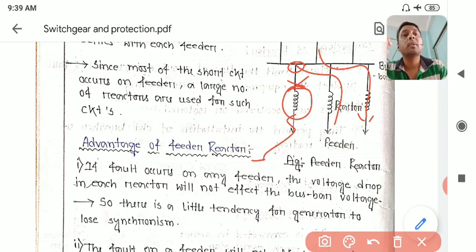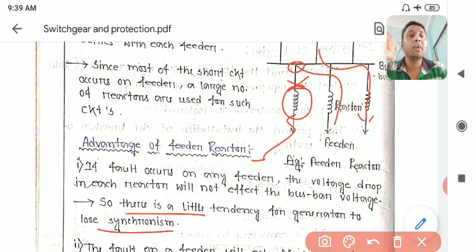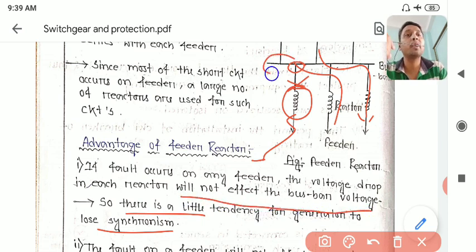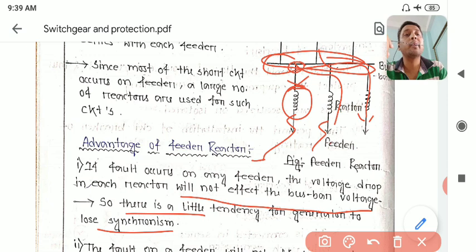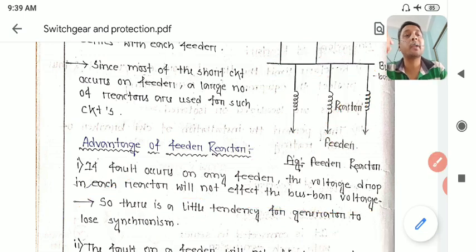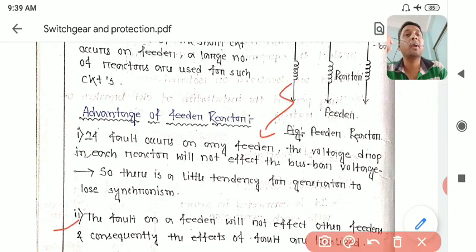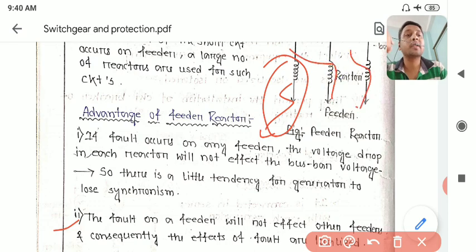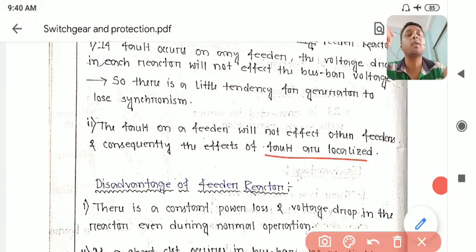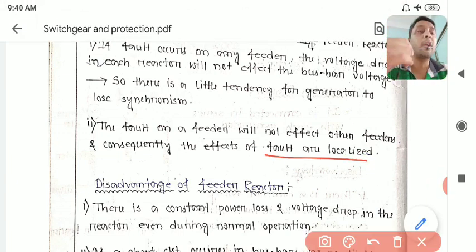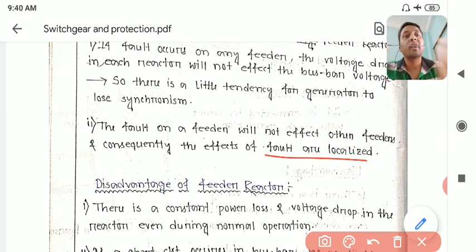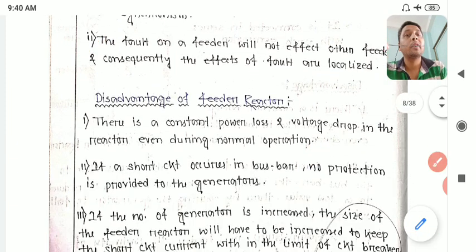Since the voltage is not zero, the generator will remain in synchronism and other feeders will continue to get current. There is only a little tendency to lose synchronism, and the voltage drop in each reactor will not affect the bus bar voltage. The bus bar voltage will not become zero due to any fault in the feeder - only that respective feeder will be affected. This is known as localizing the fault, meaning only the faulted section is eliminated while the rest of the system continues operating.